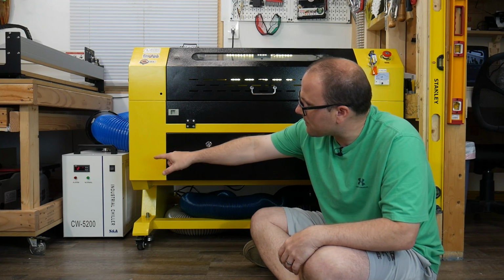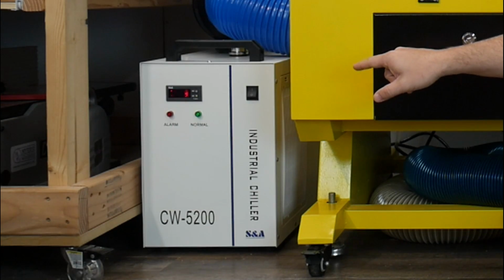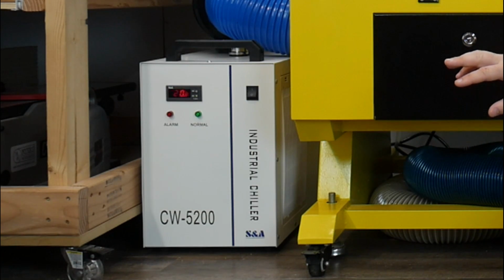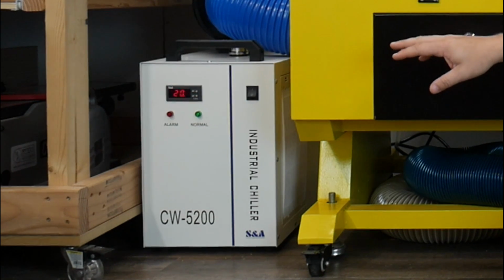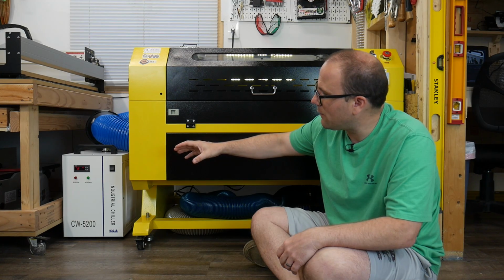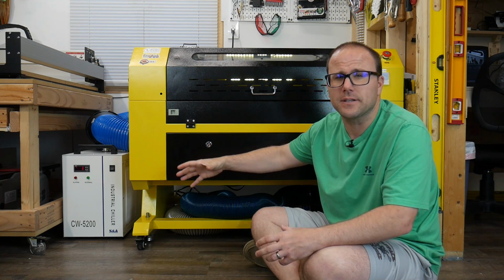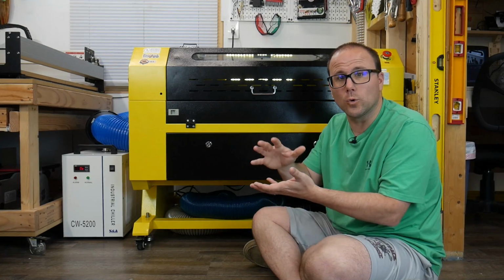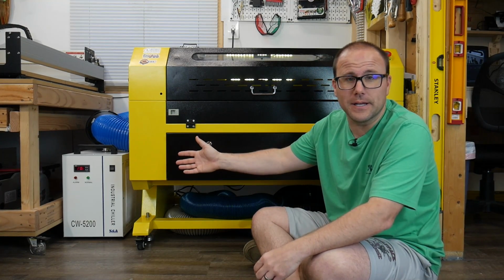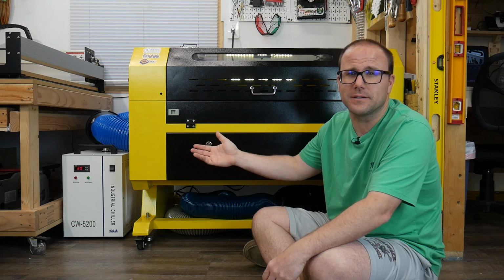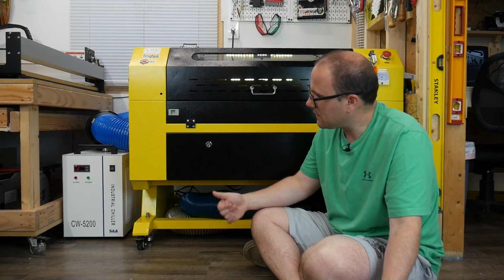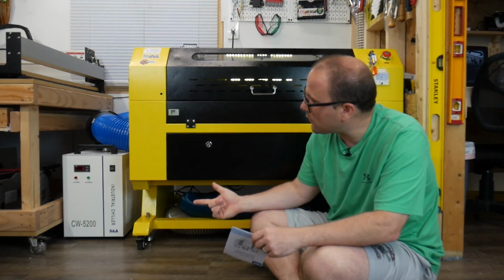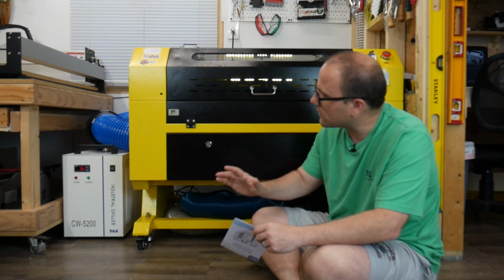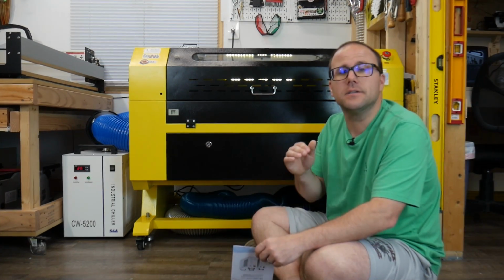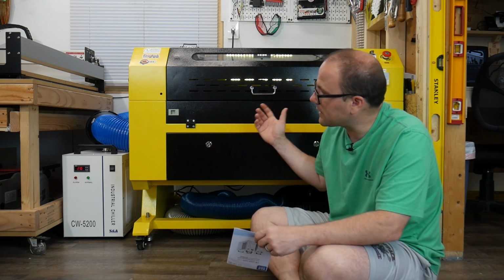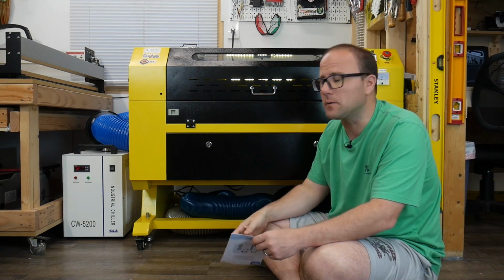So on the front, you can see over there, we're hitting 20.9 degrees Celsius, 20.8 right now. It's going to lower it to where it thinks it needs to go. This one actually has auto cooling. We don't have to go in and set it to anything, it auto does it on its own. The compressor just kicked off. We're at 20.3 degrees Celsius. So it likes to be right around 20, and that is a good range to be for running the laser and keeping it cool.